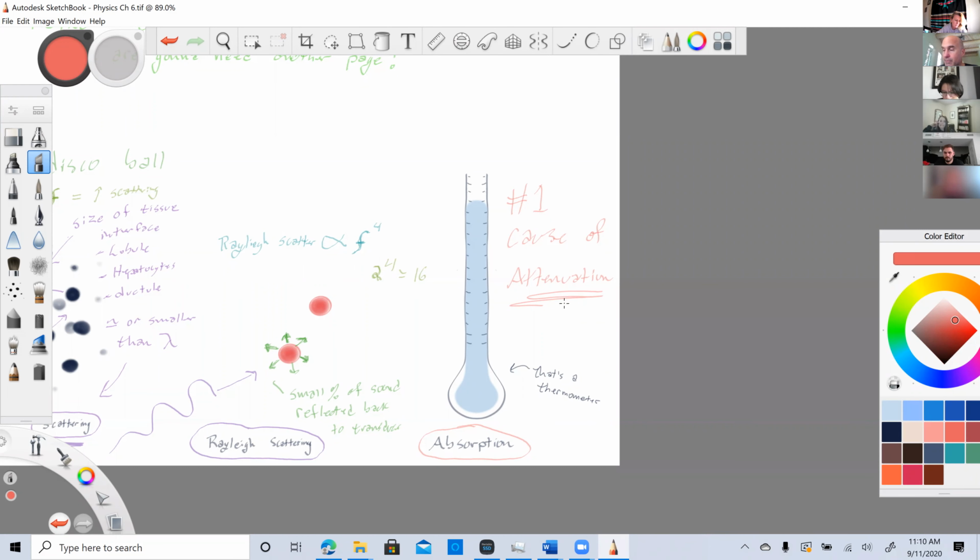But it's important to know that bone undergoes extensive absorption when we're talking about fetuses. When they start to develop bone, at first it's not bone, of course. At first, fetuses have cartilaginous bones. Their bones are made of cartilage. That doesn't absorb a whole lot of heat, but then they start to calcify, and it really starts to absorb sound. And at that point, the bioengineers and everyone who builds these machines really have to worry about how much heat we're developing. You don't want to cook the skull on a little fetus.